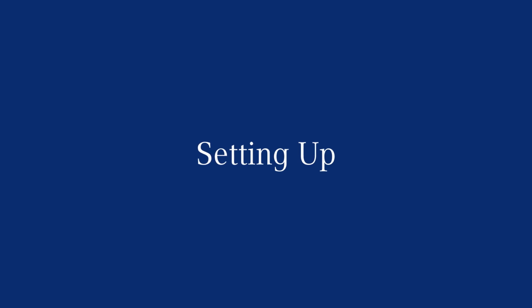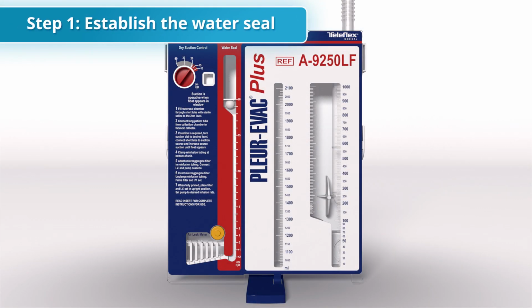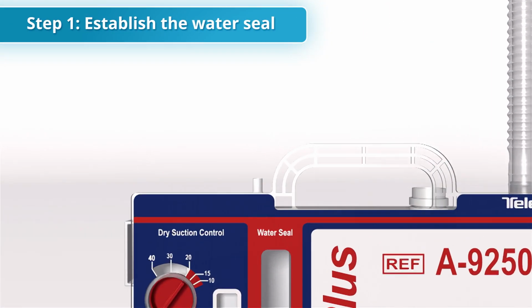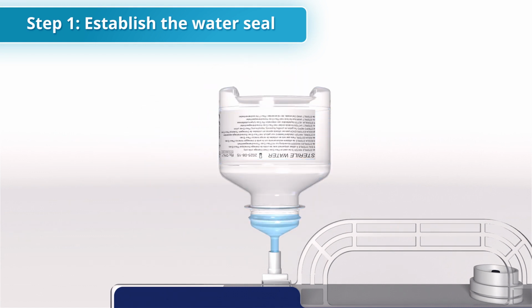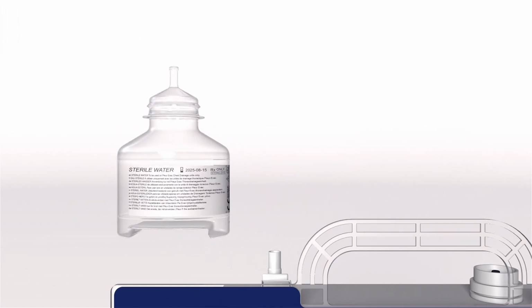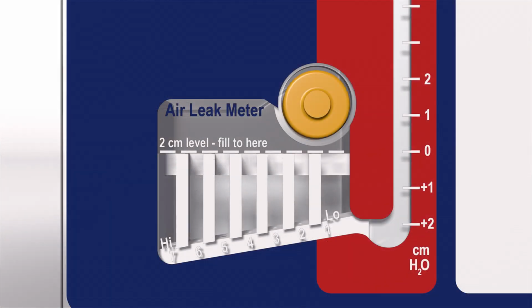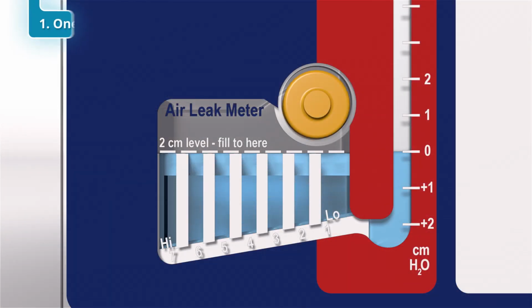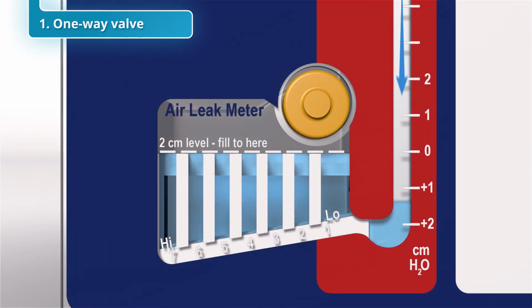Setting up the Pleur-evac Plus A9250 autotransfusion system is a four-step process. The first step is to establish patient protection by applying the water seal by filling the chamber to the 2 cm level. The water seal serves three purposes. First, with its U-tube manometer design, it acts as a one-way valve, allowing evacuation of air from the patient's chest cavity, but preventing its re-entry under normal conditions.